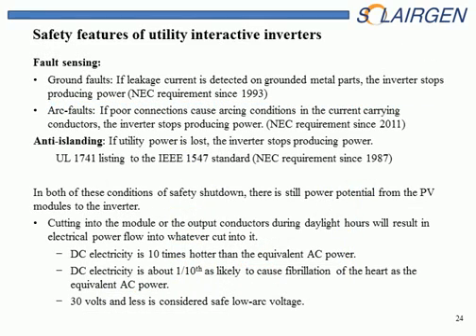What are the safety features that are built into utility interactive inverters? The IEEE 1547 standard now requires that we have ground fault, arc fault, and anti-islanding. Ground fault sensing and disconnection is whenever we have an internal breach between the parts of the PV cell, the negative and positive, to the frame or to another grounding material or a conductive material, which could cause a fire. An arc fault is where we have a poor connection.